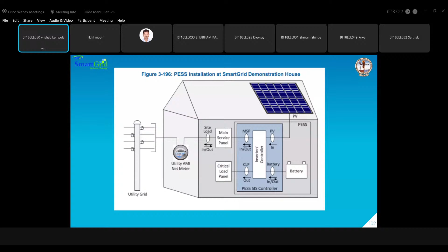These are the PESS installations of the smart grid demonstration house. Here we learn that the manufacturer recommends the battery should not be routinely charged above 95% or discharged below 10% charge level, to protect the battery and maintain its useful life. The differential in tariff rates needs to be at least 16%, which we have already covered.